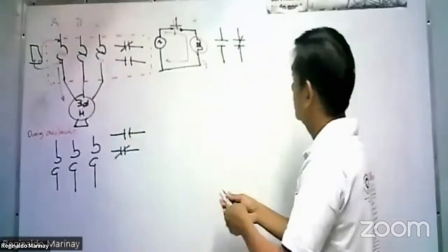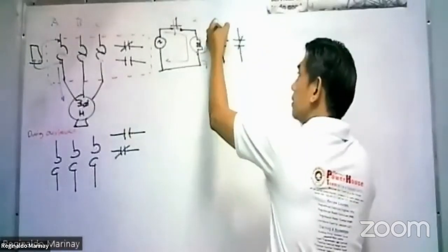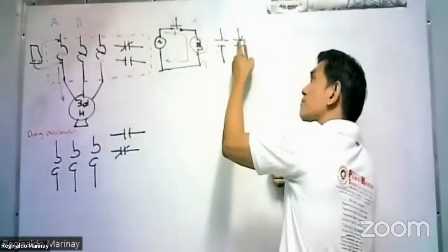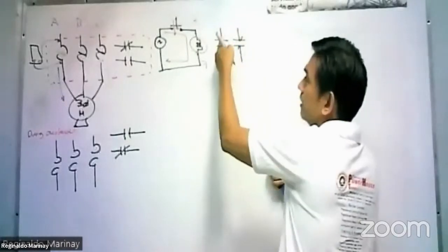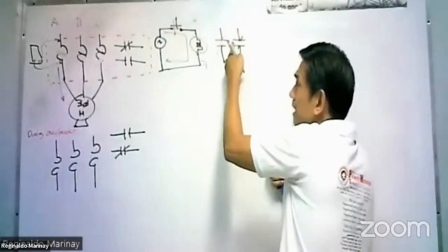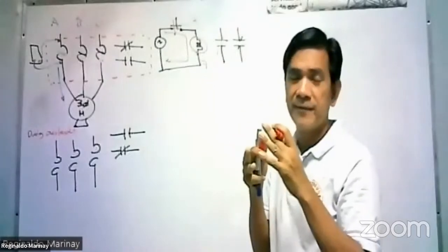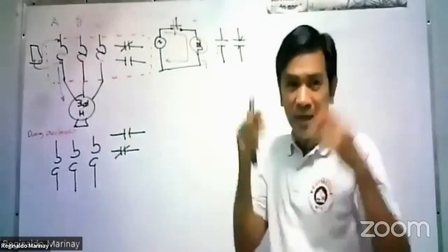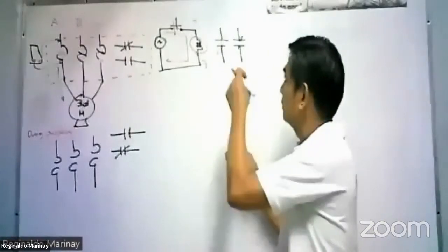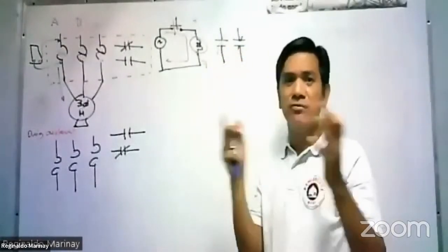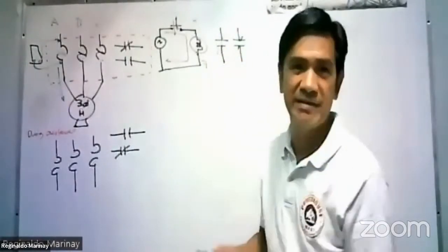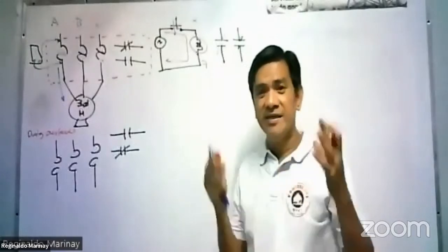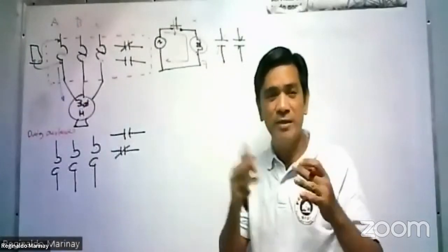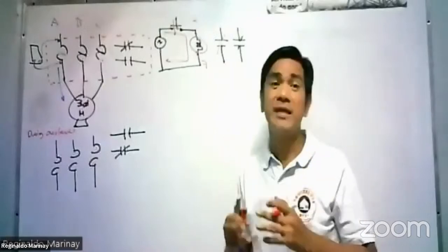This will become closed, and this will become open. The normally open becomes closed. The normally closed becomes open. When you reach the 3 seconds, it will not right away close and open this contact. No, there is a delay. You see, that is one of the basic operations of the timing relay.